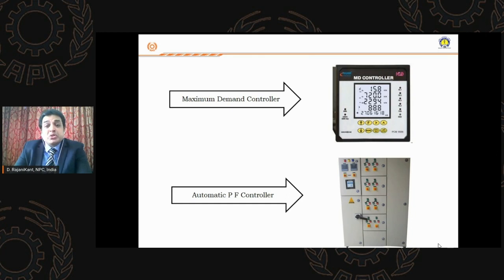So most of the SMEs were not aware, and once they see the bill, they will be shocked to see that there has been an increased bill, and they were also not aware for what reason it has been penalized. So with proper control on the demand, that means a maximum demand controller, it will control the demand once it reaches around the agreed 500 kVA of the contracted demand. Automatically it will switch off the non-essential loads. So you are always under the controlled demand as per the agreed formality with the distribution company.